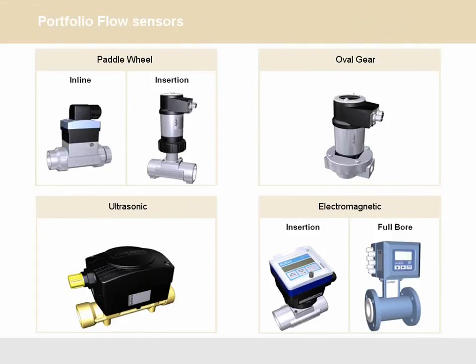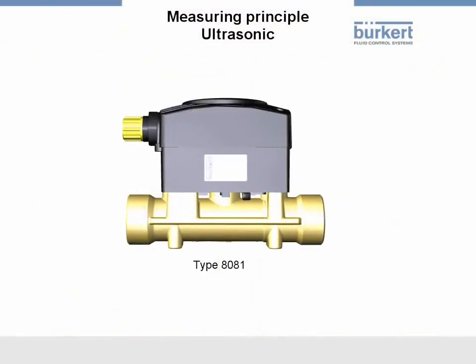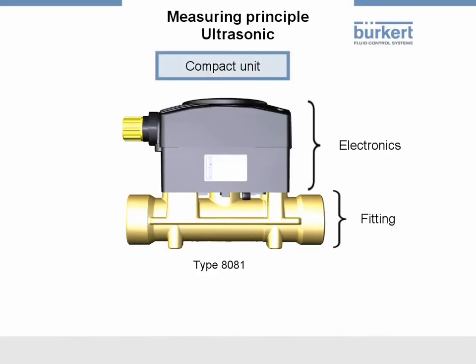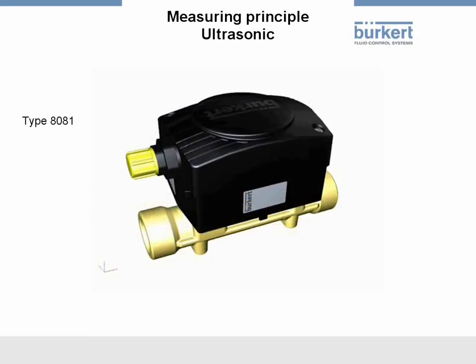The last measuring method that we'll examine is flow measurement with ultrasound. Bürkert ultrasonic sensors consist of a fitting and electronics without a display and are designed as compact units. An M12 connector is used for the electrical connection. How does flow measurement by means of ultrasonic work?